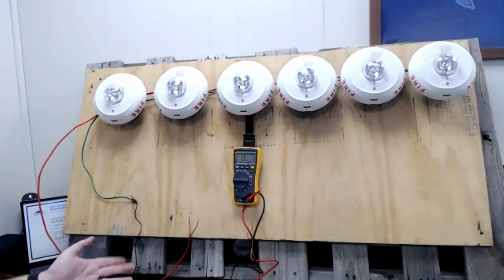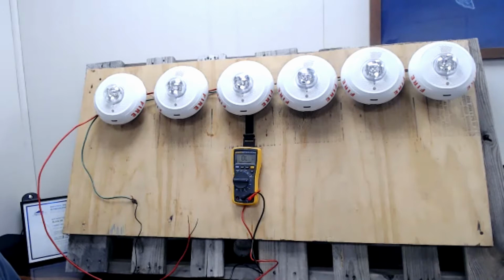So whenever we see that with our meter, the first thing we need to do is identify where the circuit's running in the field. In this case, it's very simple. We've only got one circuit and it's all right in front of our faces. But if you're on a job and you've got 4, 6, or 8 circuits running to the same room, you need to make sure you use labels. You can label it NAC 1, NAC 2, and when you're keeping your as-builts, this one's NAC 1, this one's NAC 2. And so when it comes time for this point, you can know where you're going through the building so that you can find where your devices are.